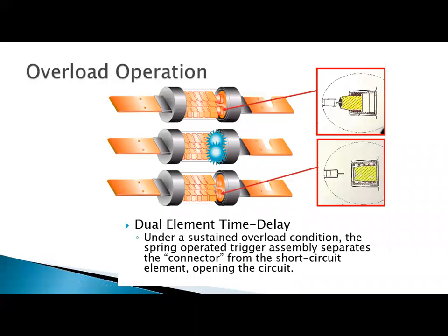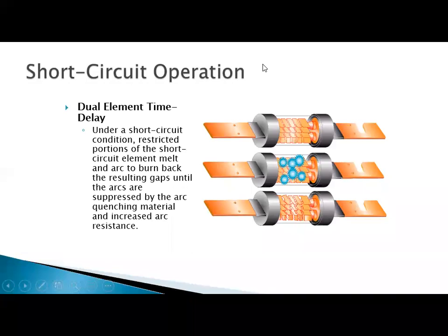On these, on the overload operation, there's basically going to be a spring in there, which is going to trigger the connector to open up, and it will just open that circuit up. So that is what's going to happen on that particular fuse. On the short circuit operation, we're actually going to melt something, and it is going to melt very quickly, and we're going to be replacing that fuse.